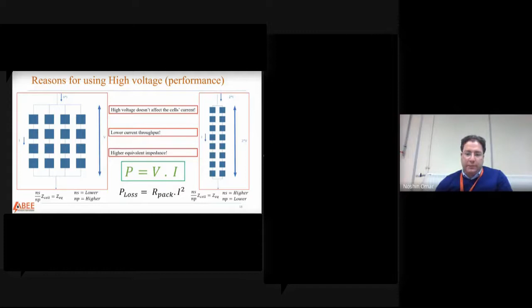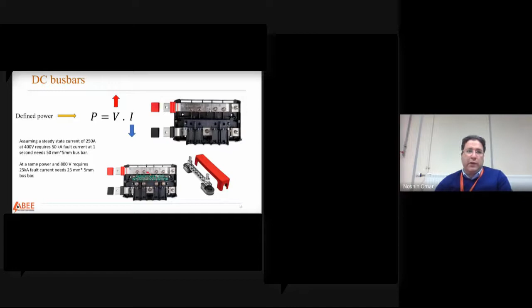Another aspect is related to the components. If you have batteries connected in series or parallel, typically through bus bars, you need to dimension the bus bars according to the current that should flow through them. For the same power, if your voltage is higher, 800 volt compared to 400 volt, your current will be almost half of that at 400 volt, which means the bus bars will be much thinner, smaller, and lighter — a very important advantage to take into account.